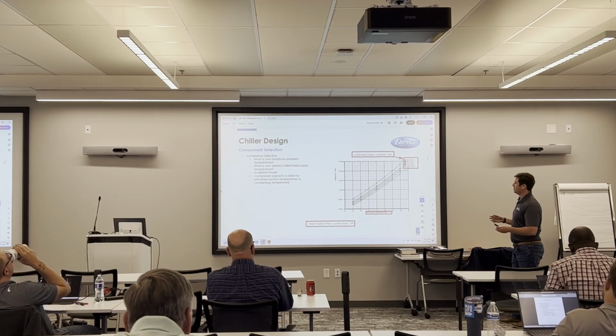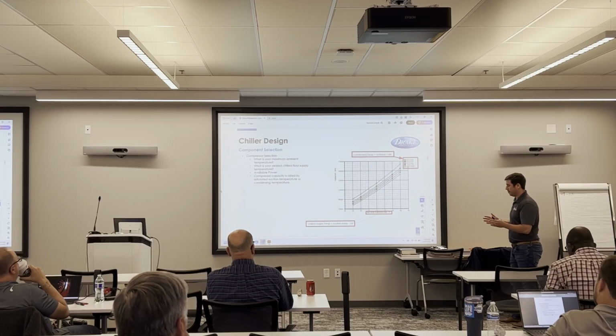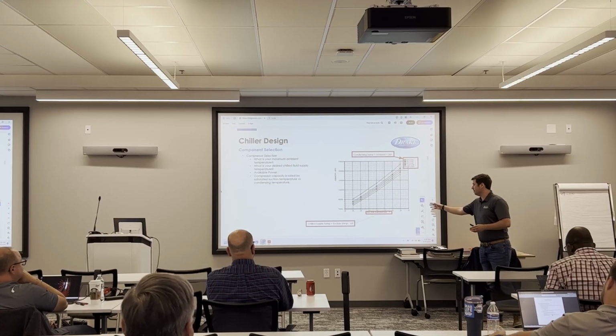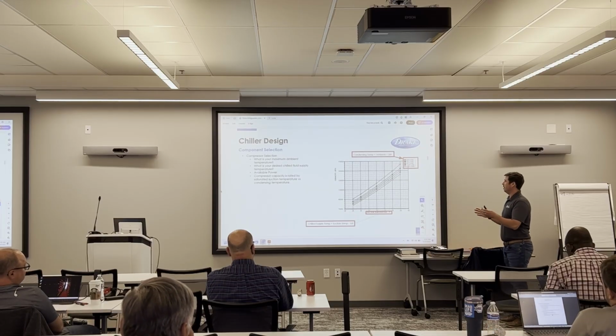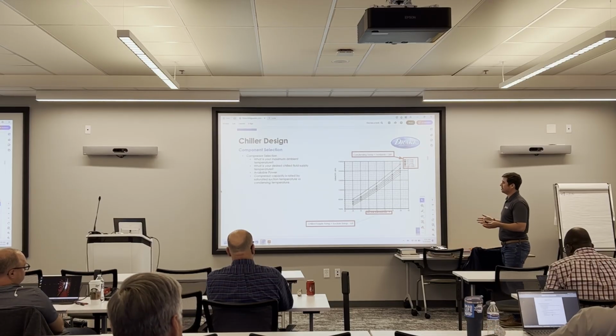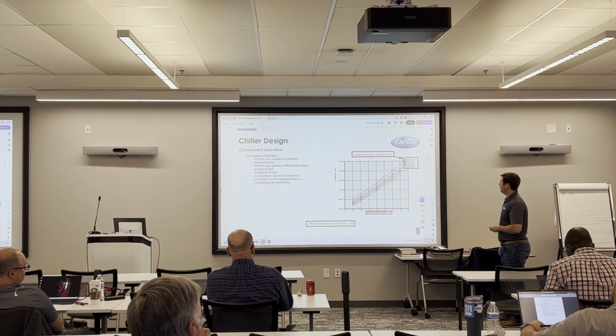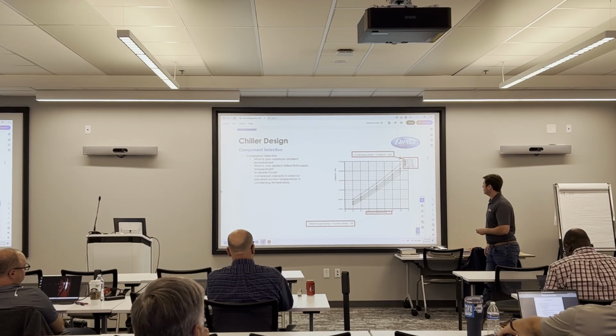So it's all about how far the compressor needs to compress. If you're starting at a high temperature suction and you're going to a low temperature condensing temp, the compressor doesn't have to do a lot of work. It can yield a higher capacity for you. All right.